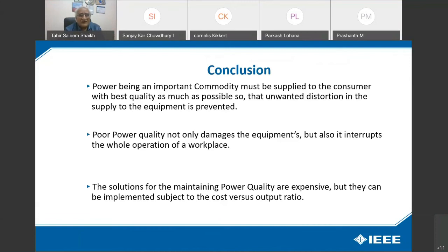But in our country, I have seen the industrial sector is most negligent on this issue. So they have a lot of problems with harmonic distortion. Sometimes the motor burns, the transmission line burns, and the AVR of a generator burns, if you have a standby generator. So you have to be very careful in giving power to your equipment.